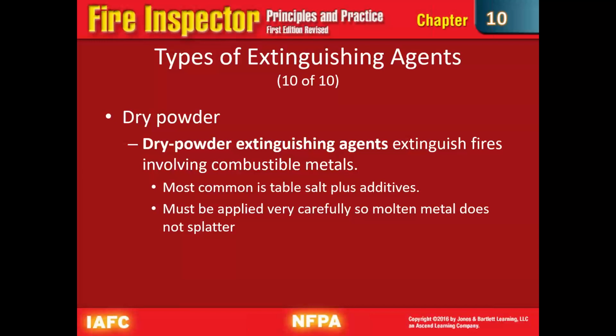If you've ever had a magnesium engine block fire, or either of the magnesium pieces on steering wheels, you put water on that, it just sprays everywhere, and it can be more hazardous. But using this helps to extinguish the fire much easier and safer. But you have to be careful. If the metal's molten, the force of the agent can cause it to spatter out.